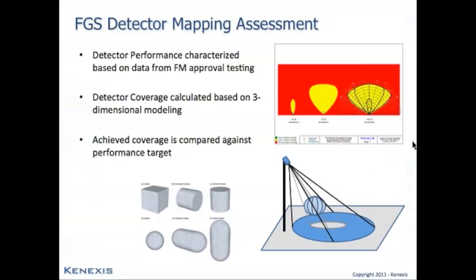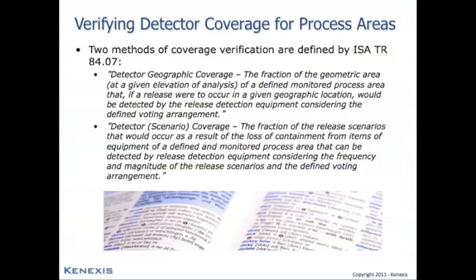Now, there are 2 methods that are defined in the ISA technical report from Working Group 7 that defines the methods and practices for performance-based fire and gas detection and suppression systems. The 2 types of coverage are geographic coverage and scenario coverage. Geographic coverage is the fraction of the geometric area at a given elevation of analysis of a defined monitored process area that, if a release were to occur in a given geographic location, would be detected by the release detection equipment considering the defined voting arrangement.